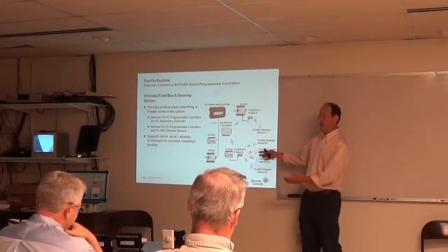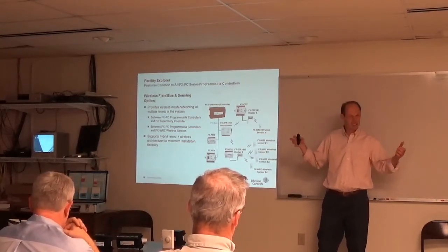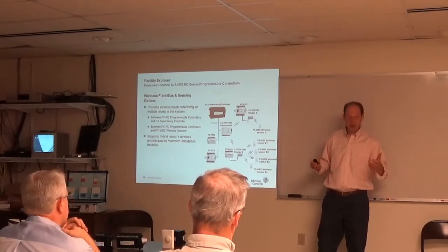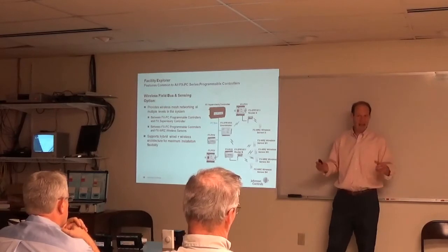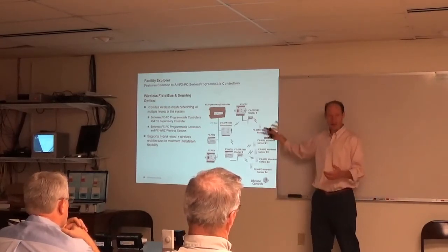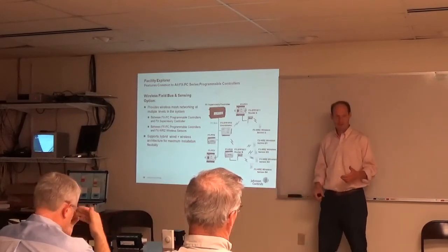So, like say if I have an FX-60, what do you put on there? Maybe 60 devices, maybe on the 70s you put maybe 100 devices, on the 30s maybe 20, 30 devices, depending upon how many points you're going back and forth, how many graphics, how many trends. Same amounts here. It's all the same. You can do multiple coordinators.